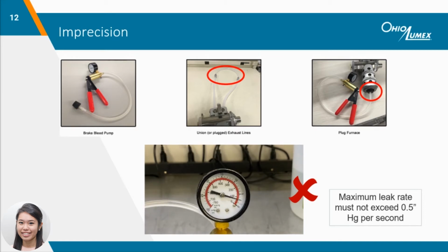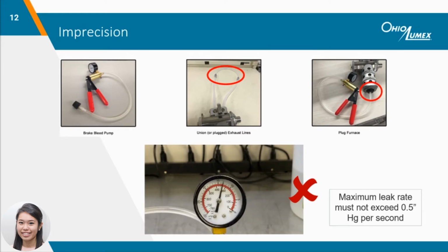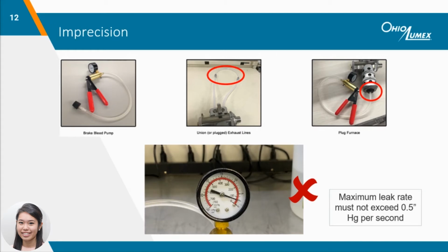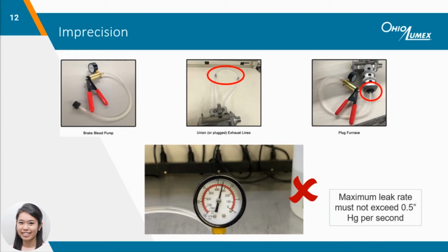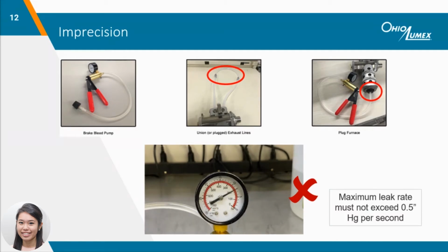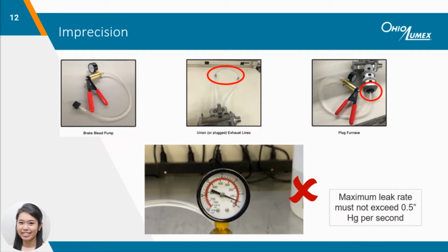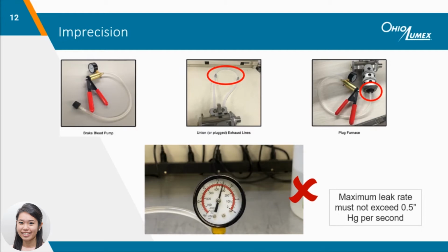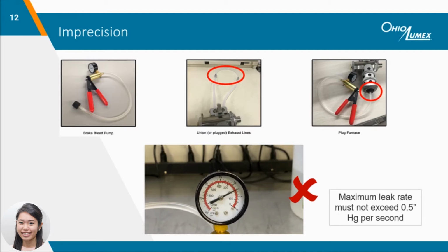The video of the vacuum gauge indicates the attachment has a large leak that will need to be found and repaired. The most common location for a leak is at the window collars. Make sure the graphite gaskets in quartz windows are not cracked, crimped, or pushed up against any particulate, and the window collars are tightened a quarter past hand tight.